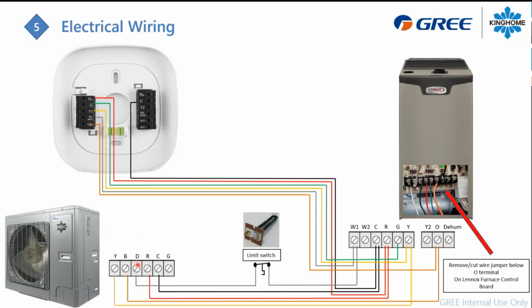If you will use the D terminal, I can suggest what I did in the past when working with a gas furnace. The D terminal here can be plugged into a limit switch. What we've done is this kind of limit switch can be installed between the A coil and the furnace. So somewhere under the A coil, but after the furnace. You need a perfect spot in the supply duct. This is a normally closed limit switch, and it can open at 100 degrees Fahrenheit, for example.